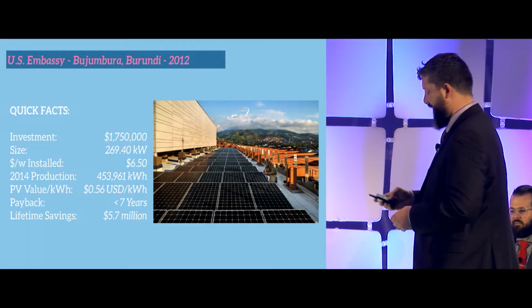We took the generator plant, since we're again on prime power running generators 24/7, and made the generators smaller, stretched them out, and paralleled them so that it's demand response. As the load increases, generators come online, and as it decreases or as we improve in production, they come offline. This is very good on a prime rated system, because if you can turn off a generator, you're saving all of that fuel. Going from 80% to 70% efficiency, or reducing the load by 10%, doesn't do a whole lot when you're talking about running big generators, but if you can turn one off, you get significant savings.